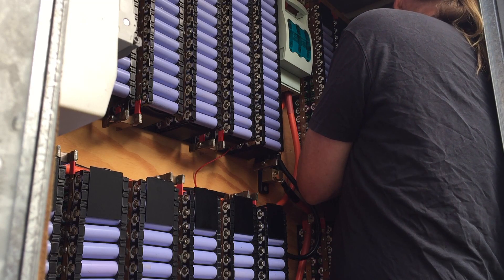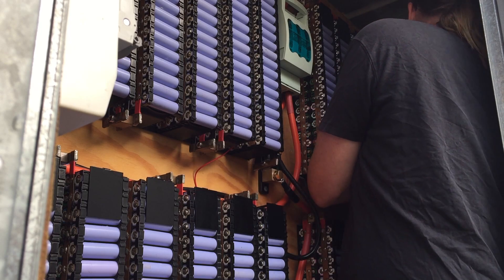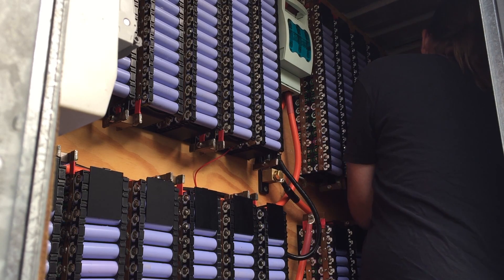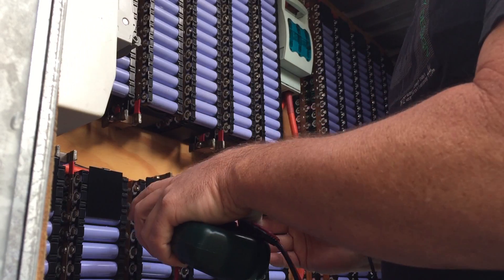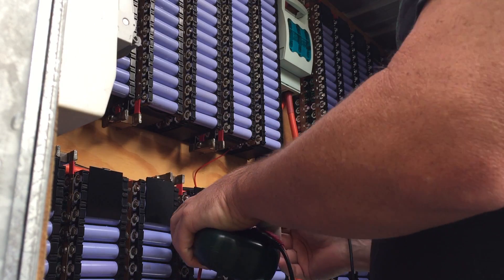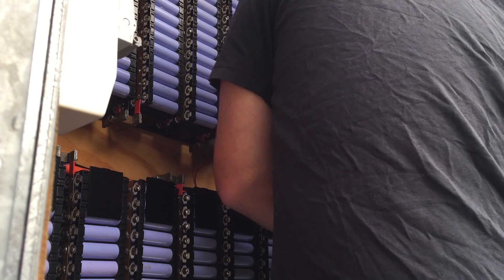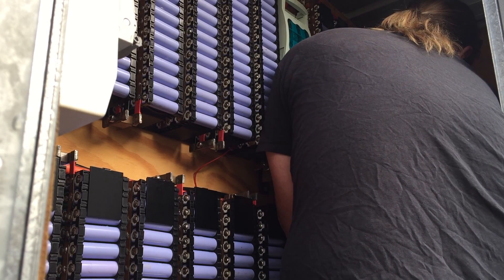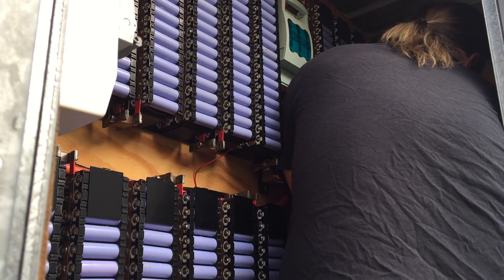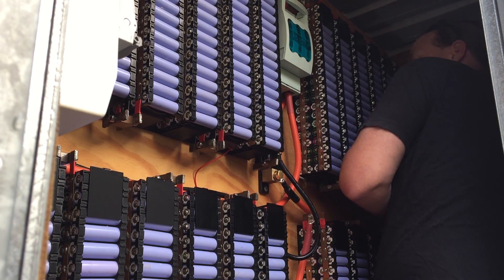Now this is the bad cell that was one volt, and it is now 2.8 volts. Continuing: 3.6, 3.66, 3.62, 3.58, 3.63, 3.71, 3.62, 3.6, 3.62, 3.63, 3.53, 3.5, 3.46, 3.68, 3.58, 3.68, 3.6, and 3.66.